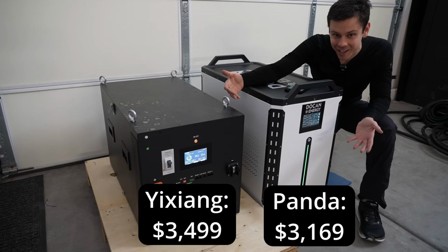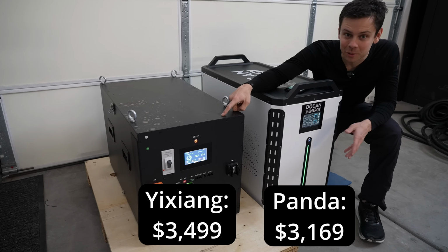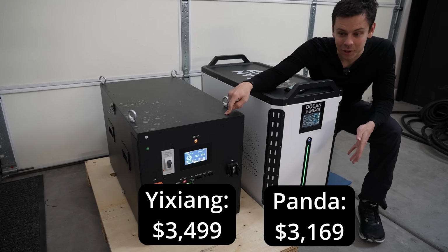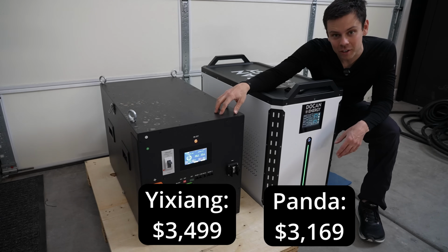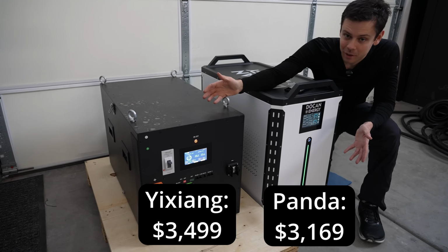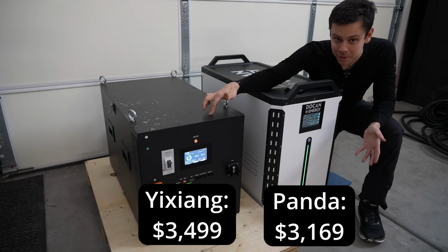But which one would I choose? This one has thick, flexible copper bus bars. It can handle more current, and the build quality is better. You don't have 2 conductors going to every bus bar. You have potted ring terminals for the temperature sensor.